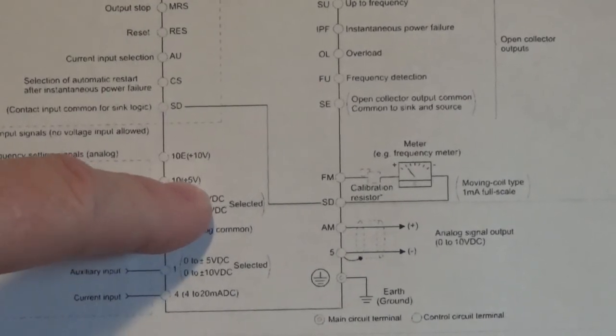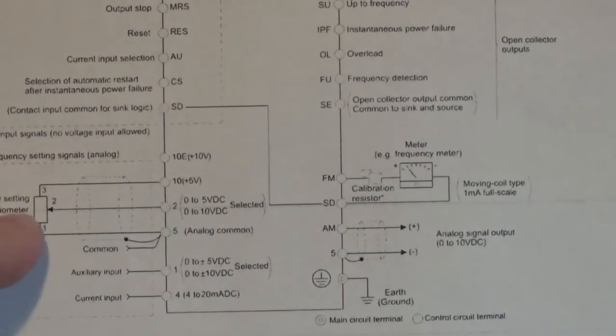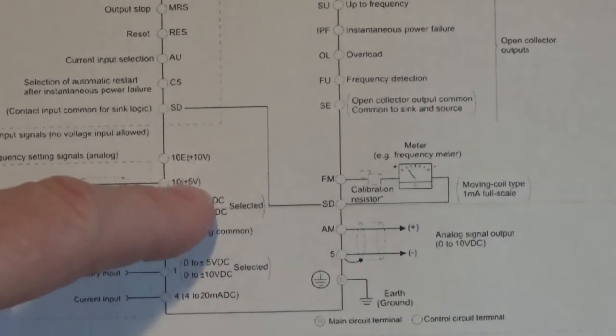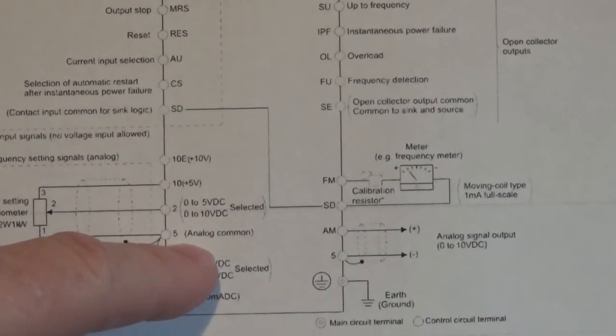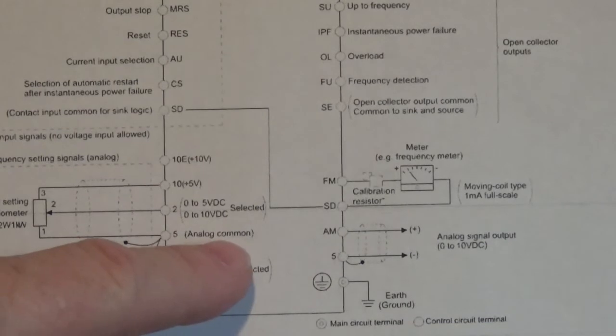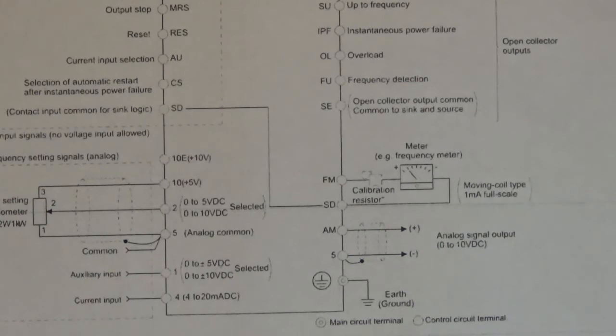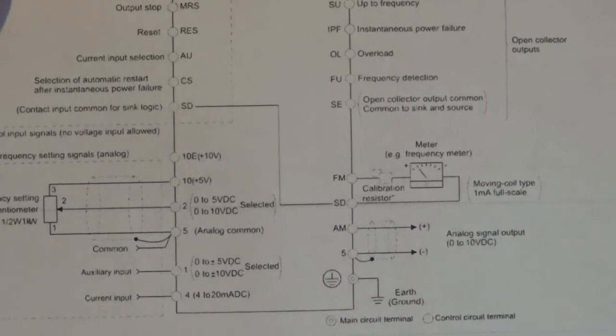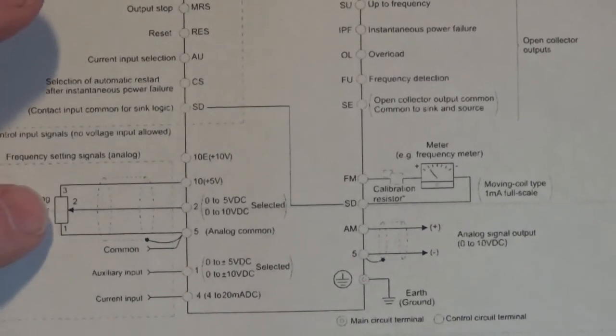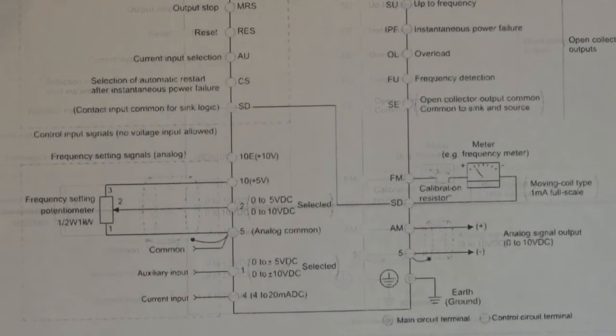And since we're coming off of terminal 10, we're going to have 5 volts going in here when we max that pot out. Now terminal 5 is your analog common. And those are the three terminals that you connect your speed reference to. All right.